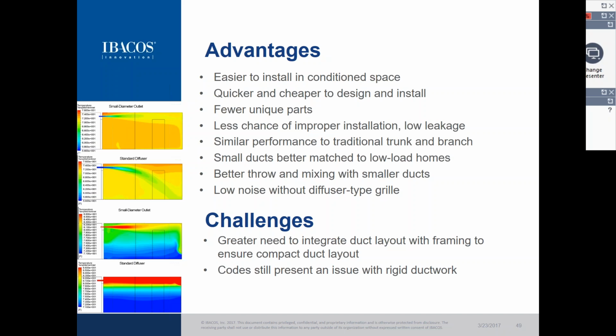With the ductwork being installed within conditioned space, there is less of a risk of condensation and mold growth. If there was some scenario where air sealing wasn't done well and you had extra humid air in a floor cavity, there could be some concern there. That would be part of the ultimate design of this duct material, to understand the limits of surface temperature, and that may necessitate a small amount of insulation contained within the diameter of the ductwork to ease some of those condensation concerns. So certainly something we're aware of, wasn't specifically targeted here, but something we're thinking about moving forward.